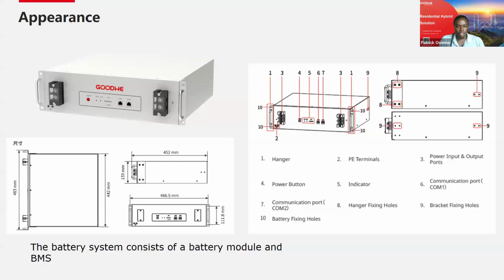On the interaction side, there are LEDs at the front to give you the state of charge and the status, whether the battery has an alarm or is running correctly. We have a start on-off button, ports for connecting the DC cables, and communication ports for daisy chaining as well as communicating to the inverter. You can see the battery is quite sizable, so it's easy to fit in terms of mounting as well.